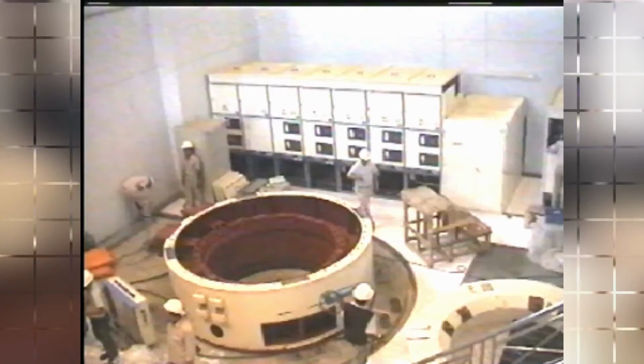The speed of the generator is 500 revolutions per minute. The generator is designed for speed rise up to 155% of the rated speed and to withstand the maximum runaway speed of 990 revolutions per minute for not less than 5 minutes. Direction of rotation, clockwise. The stator frame is supported on and grouted to the power plant foundation. The stator frame will sit on sole plates laid on a concrete beam in the power plant foundation with the generator housing. The concrete beam will form part of the generator floor.